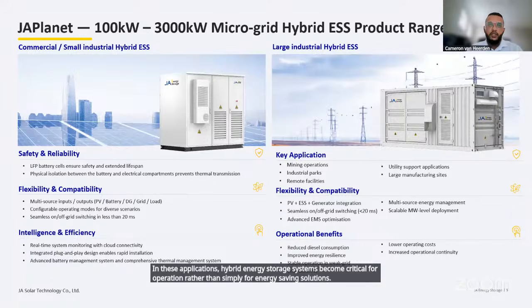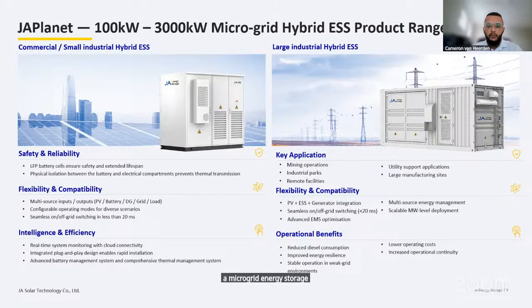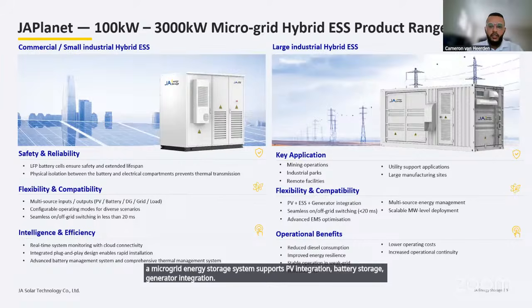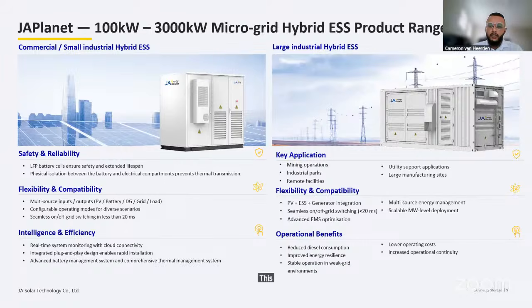Our microgrid energy storage system supports PV integration, battery storage, generator integration, as well as intelligent EMS control. One key capability is seamless on and off grid switching under 20 milliseconds, allowing the facility to maintain stable operation during grid disturbances and outages.